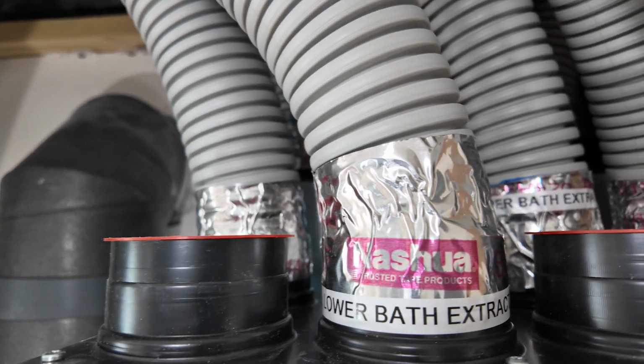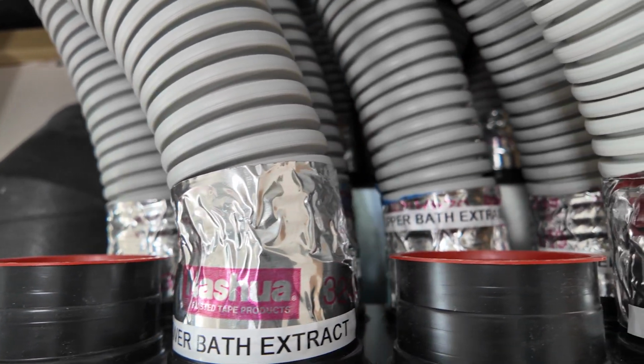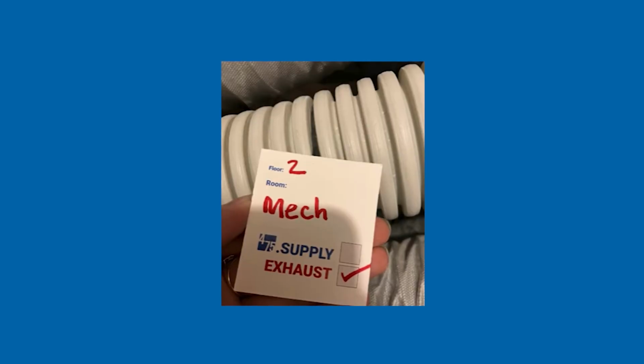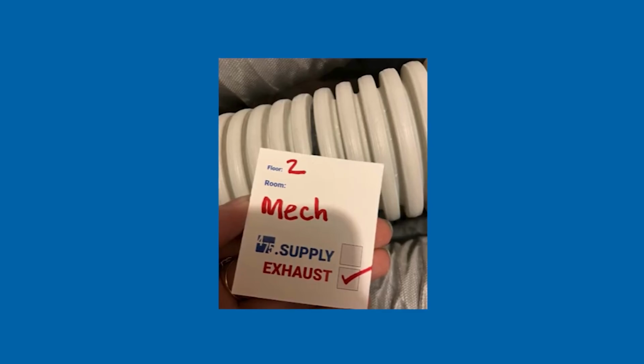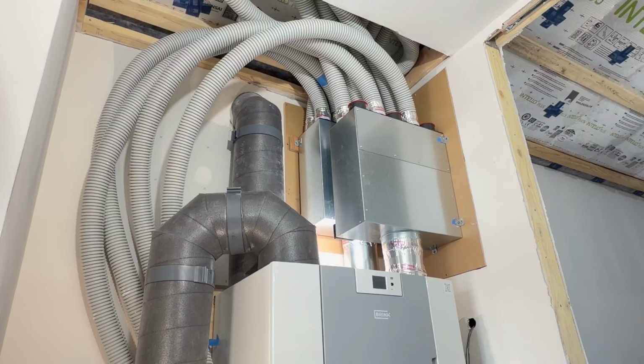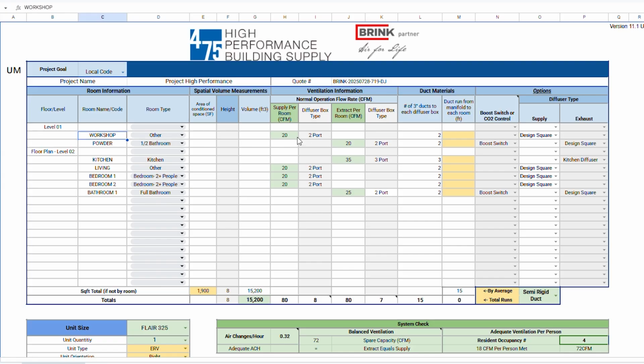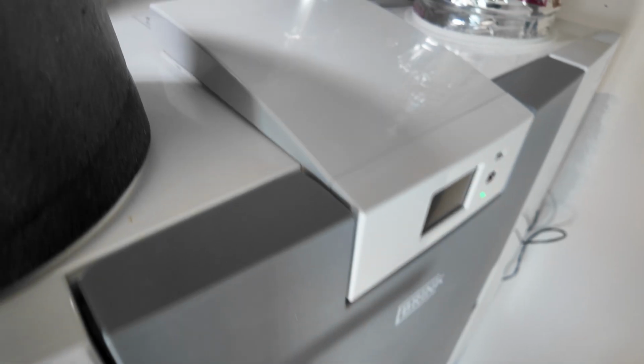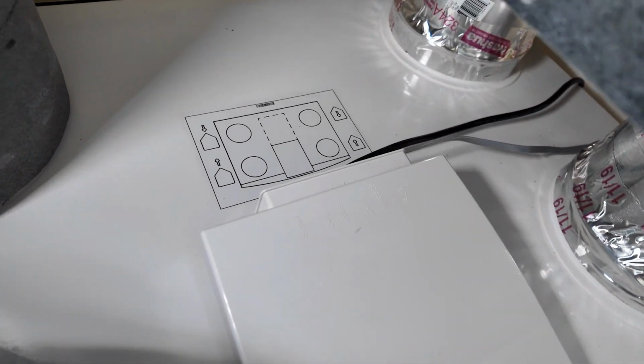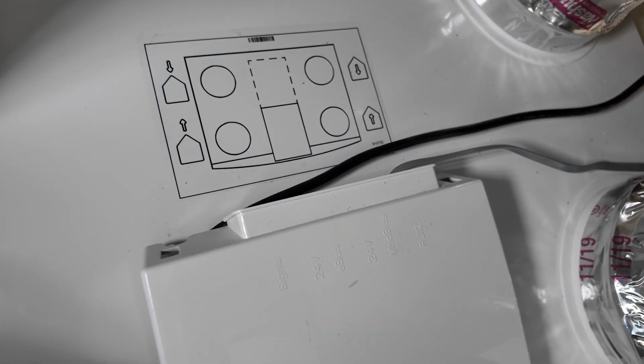All ducts should be clearly labeled according to the rooms they serve. 475 supplies duct tags to make this easy. Verify that all living spaces are connected to the supply manifold, and that all rooms requiring extract are connected to the extract manifold. This layout should match the design documentation. Then confirm that the manifolds are connected to the correct ports on the unit.